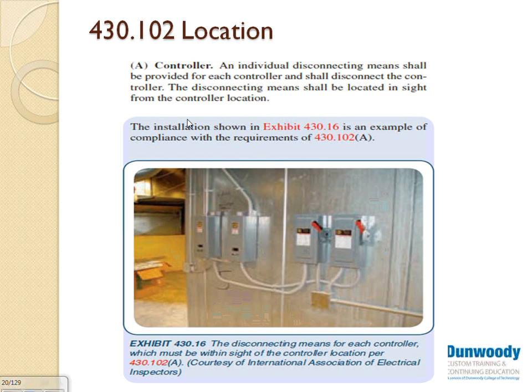Disconnects. Motors, guys, are notoriously famous for having a disconnect. Here's the rule for disconnects. Every motor must have its own disconnect within sight of the motor, within sight of the controller, and within sight of the machine driven by the motor. Because we can have a motor here, the controller there on the wall, and the machine in another area. The general rule is to have a disconnect within sight of the three of them. That's okay. Within sight is 50 feet or less, no obstacles. So you have a disconnect there that disconnects the controller, the motor, and the driven machine. That's one. If you can't achieve this, then you have to have a disconnect for the motor, a disconnect for the controller, and a disconnect for the machine.